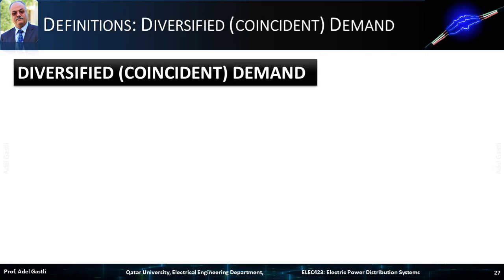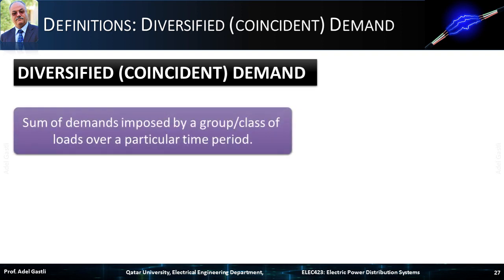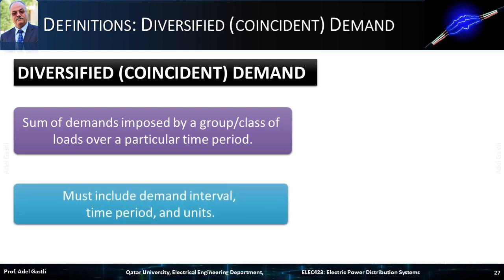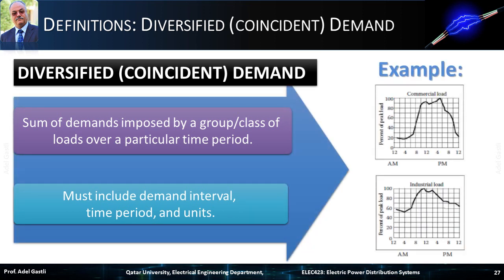Now we will define the diversified or coincident demand. It is the sum of demands imposed by a group or class of loads over a particular time period. Similarly, it must include demand interval, time period, and units. For example, these graphs show the load curves for commercial and industrial loads, where the loads are grouped by class and their sum demands are calculated and plotted over 24 hours.